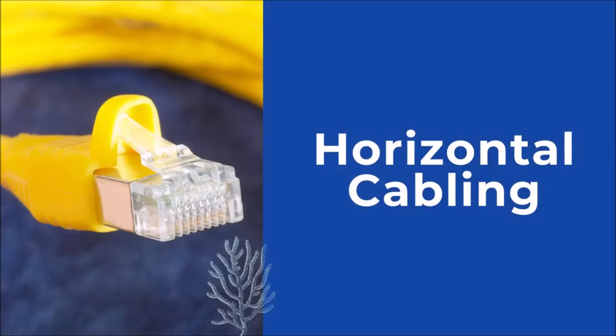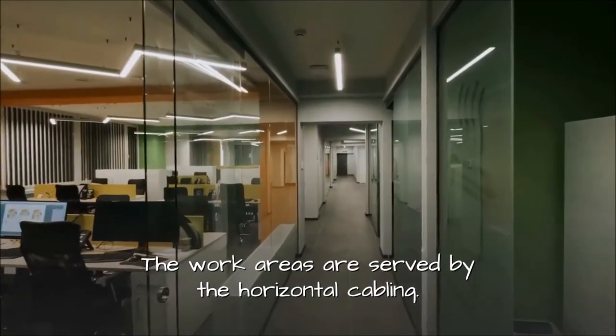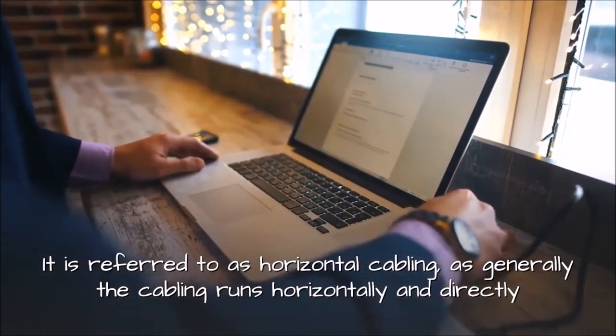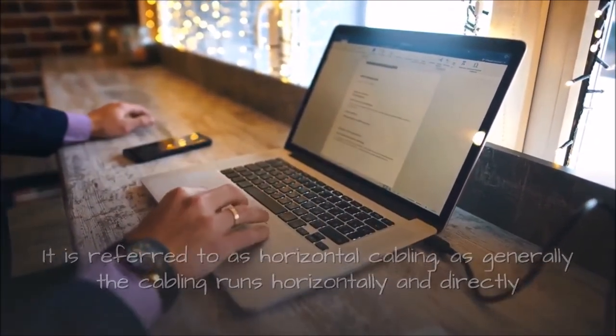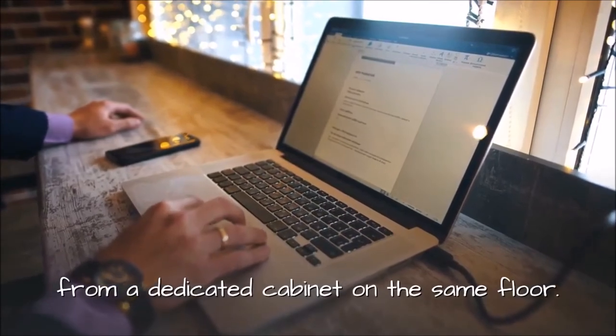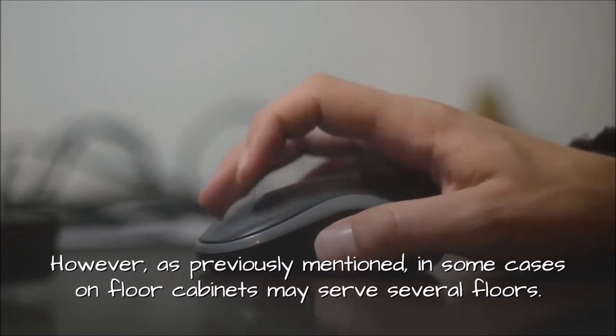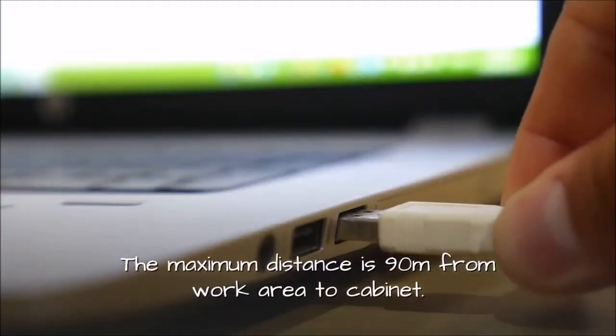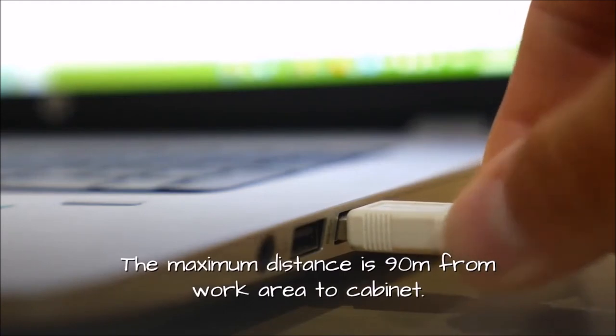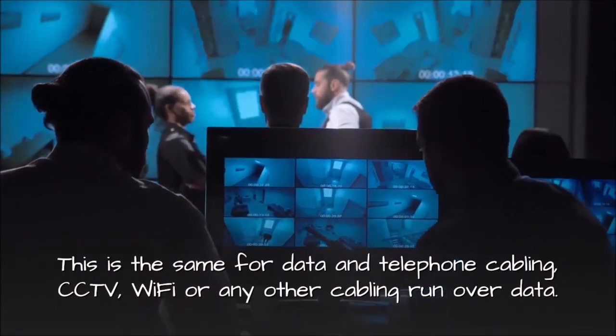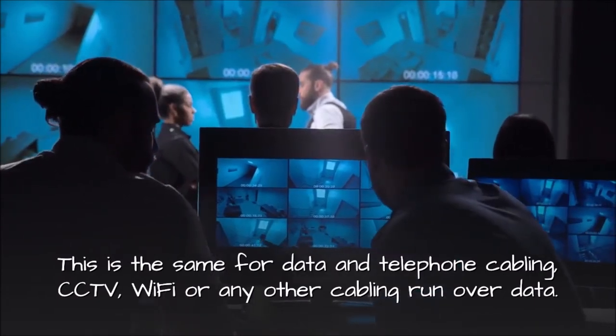Horizontal cabling. The work areas are served by the horizontal cabling. It is referred to as horizontal cabling, as generally the cabling runs horizontally and directly from a dedicated cabinet on the same floor. However, as previously mentioned, in some cases on floor cabinets may serve several floors. The maximum distance is 90 meters from work area to cabinet. This is the same for data and telephone cabling, CCTV, Wi-Fi or any other cabling run over data.